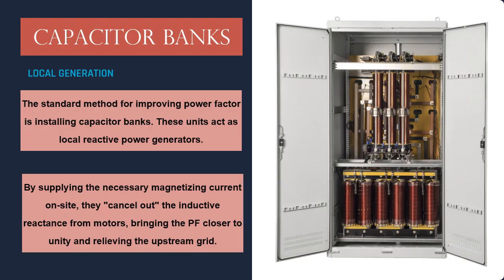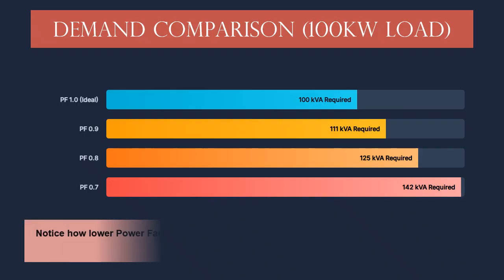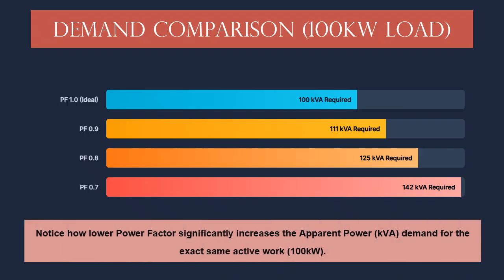Demand comparison. Let's look at the hard data. This chart represents a fixed 100 kilowatt load. At a perfect power factor of 1.0, you only need 100 kVA of capacity. But watch what happens as efficiency drops. At a power factor of 0.7, that same work requires 142 kVA of capacity. That is over 40% more strain on your infrastructure to achieve the exact same output. That is the hidden cost of a low power factor.